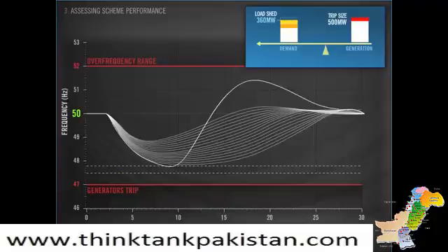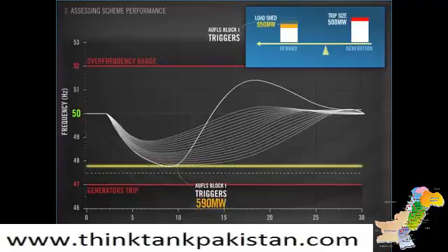Here is the first event that triggers AUFLS Block 1. We have a 500 megawatt loss of generation, which results in a total of 950 megawatts of load being shed. This includes both interruptible load and AUFLS. It is worth noting that during an event, the system is not static, and most generators are increasing their output in response to the frequency falling. The amount of load shed needed is unlikely to equal the size of the event exactly. In other words, it's not one for one.